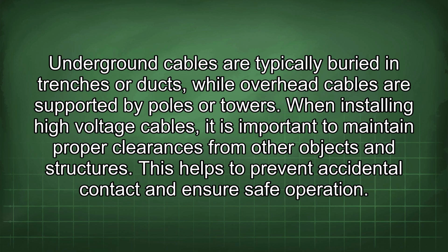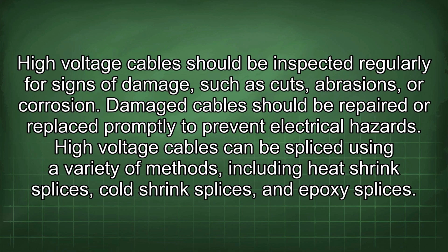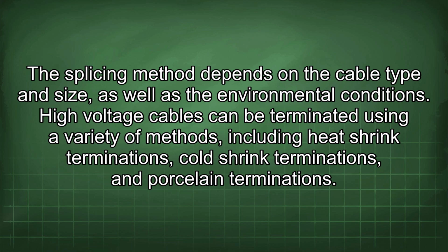When installing high voltage cables, it is important to maintain proper clearances from other objects and structures. This helps to prevent accidental contact and ensure safe operation. High voltage cables should be inspected regularly for signs of damage such as cuts, abrasions, or corrosion. Damaged cables should be repaired or replaced promptly to prevent electrical hazards. High voltage cables can be spliced using a variety of methods, including heat shrink splices, cold shrink splices, and epoxy splices. The splicing method depends on the cable type and size, as well as the environmental conditions.